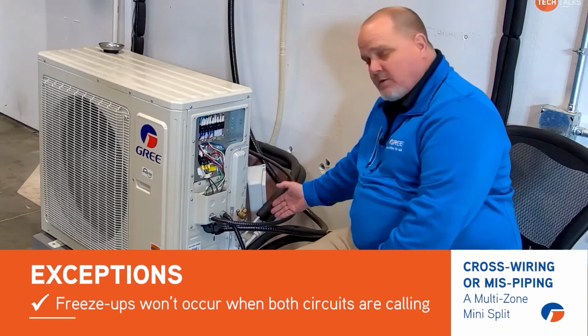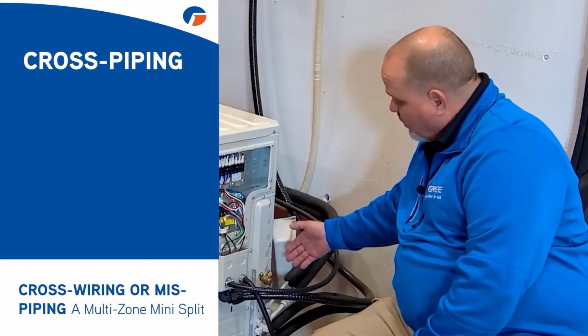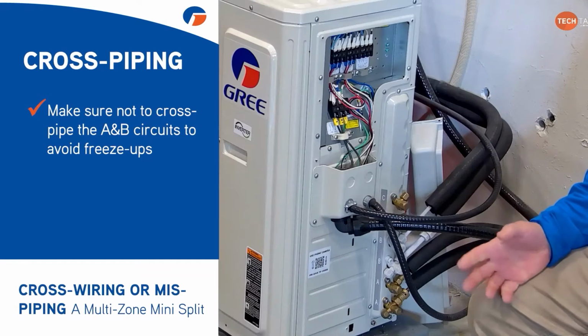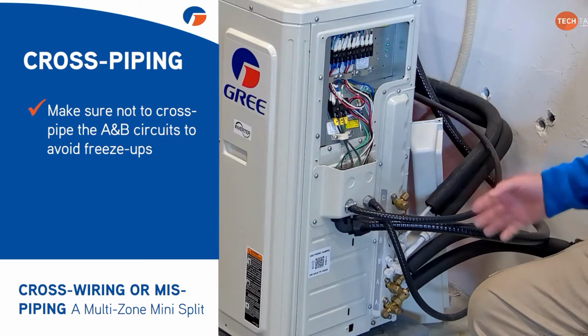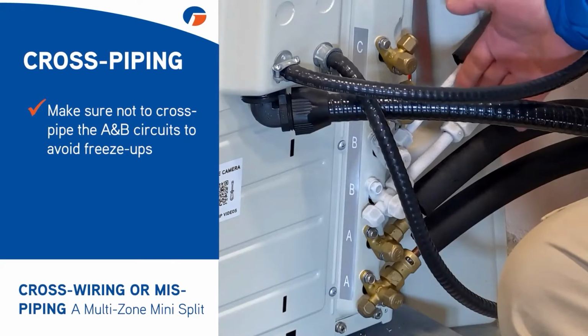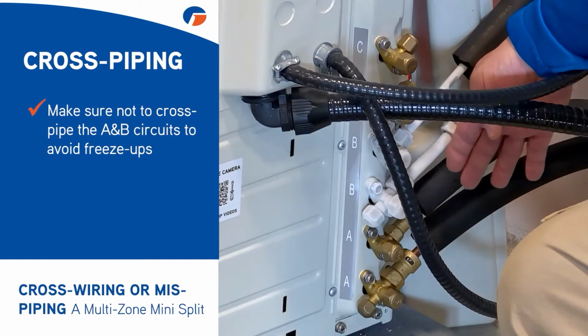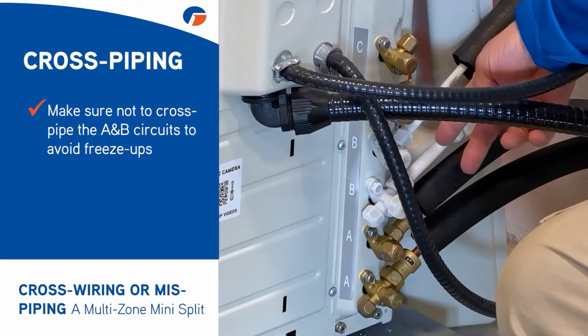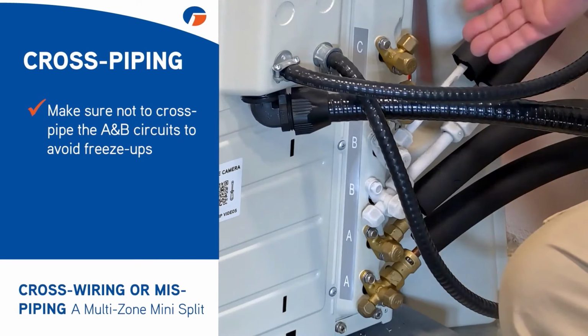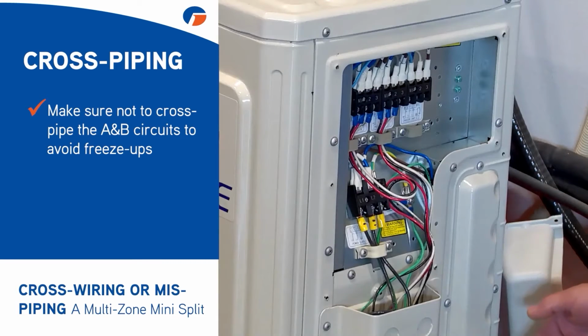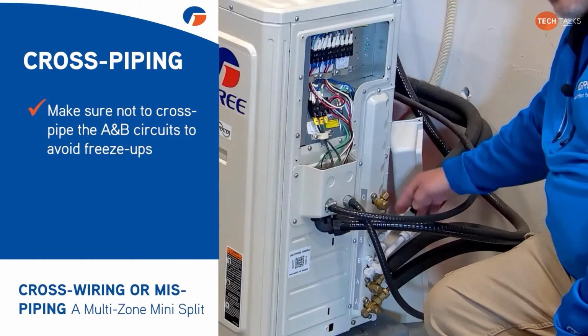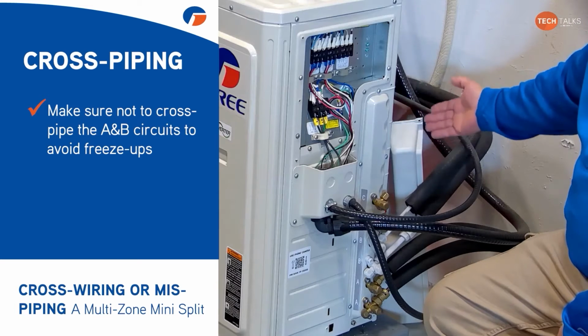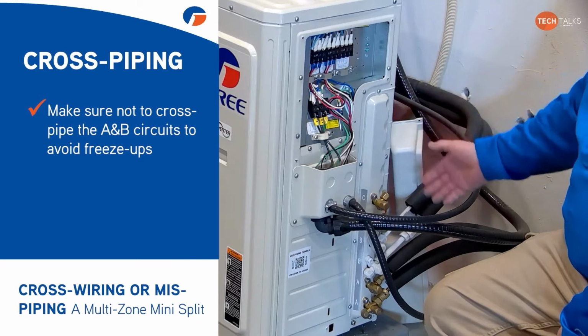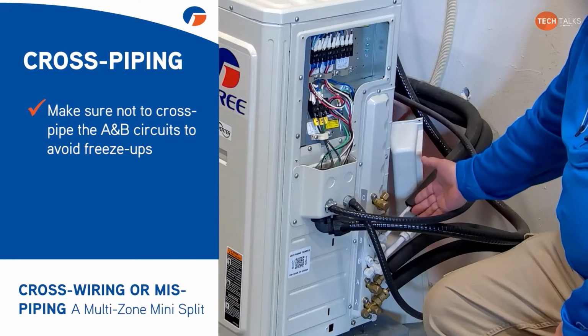The other thing you want to keep in mind is that we don't want to cross the pipes either. When you're laying out your piping and your wiring, make sure you're not switching the gas pipe from, say, the B circuit with the gas pipe that's on the A circuit. If you crisscross those two, you're going to have flow problems the same way and can have freeze-ups. Same as if we cross the liquid pipe, or the small pipe as it's a lot of times referred to. If you cross those up, you're not going to flow the refrigerant into the right head again, and you're going to end up with frozen lines again.